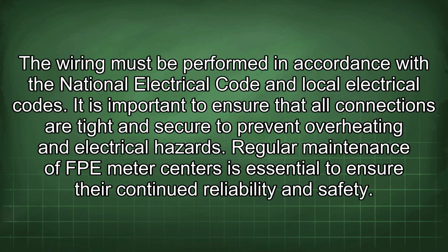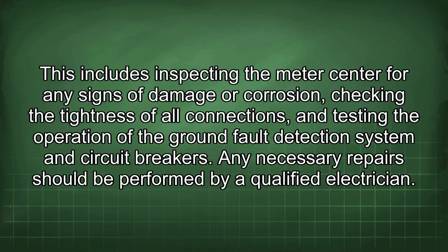Regular maintenance of FPE meter centers is essential to ensure their continued reliability and safety. This includes inspecting the meter center for any signs of damage or corrosion, checking the tightness of all connections, and testing the operation of the ground fault detection system and circuit breakers. Any necessary repairs should be performed by a qualified electrician.